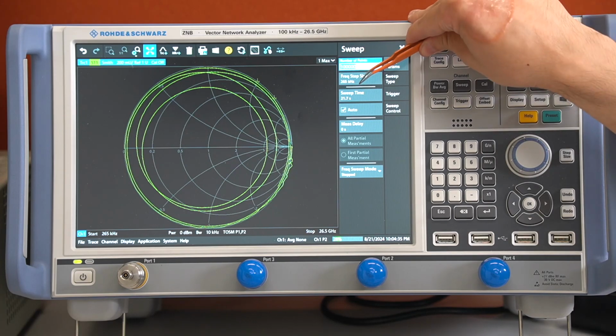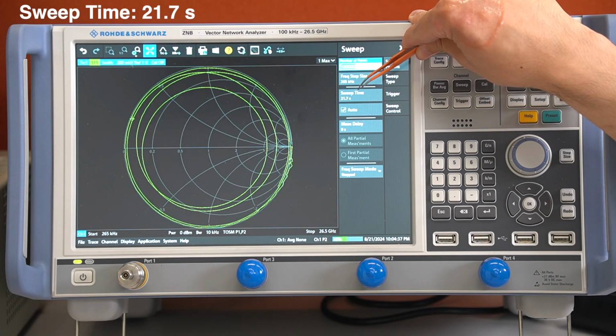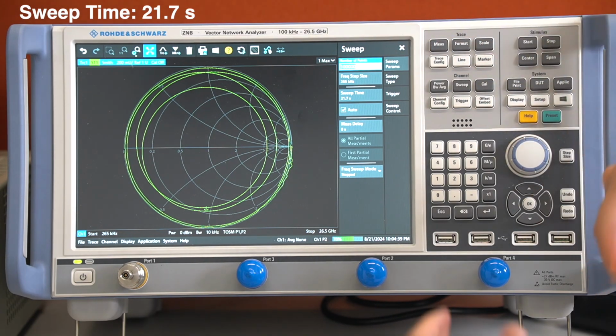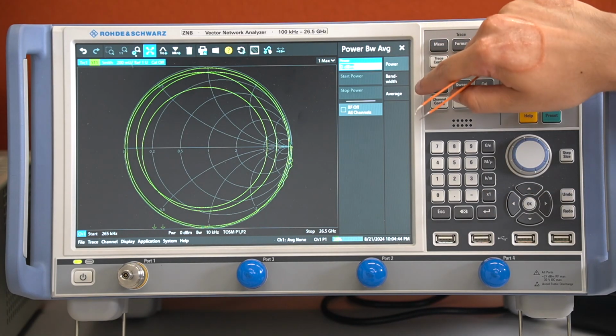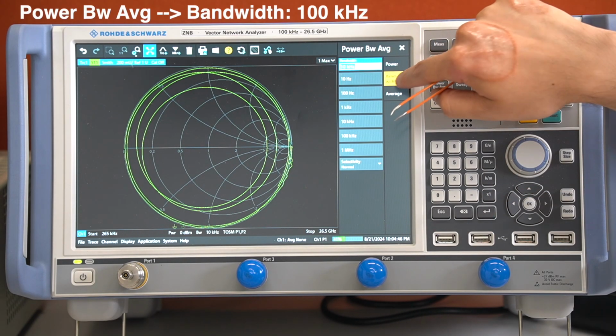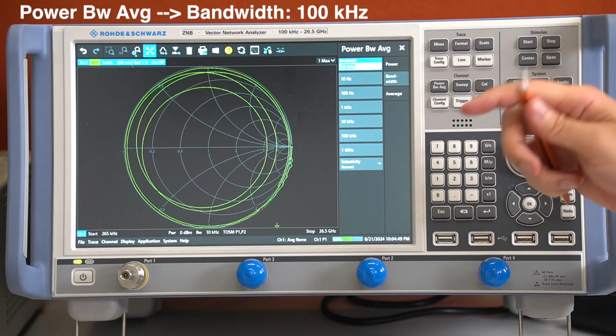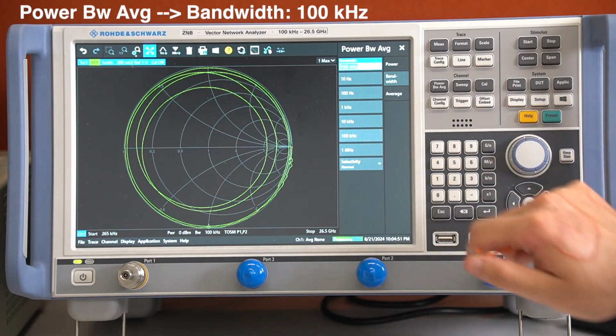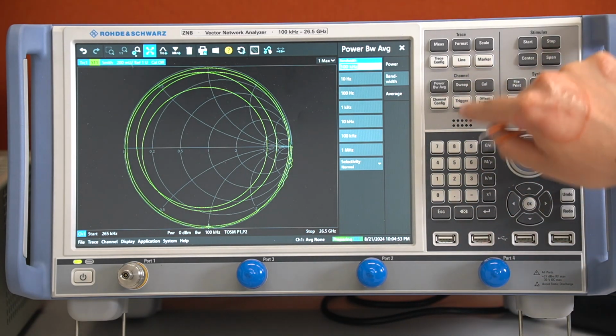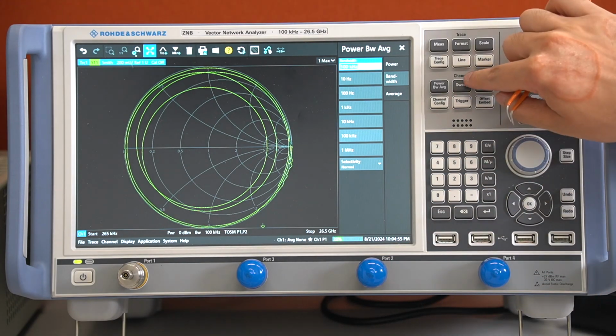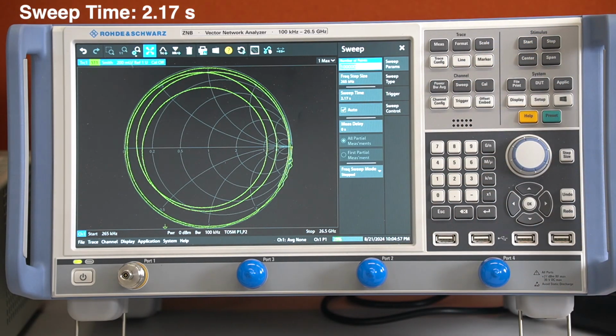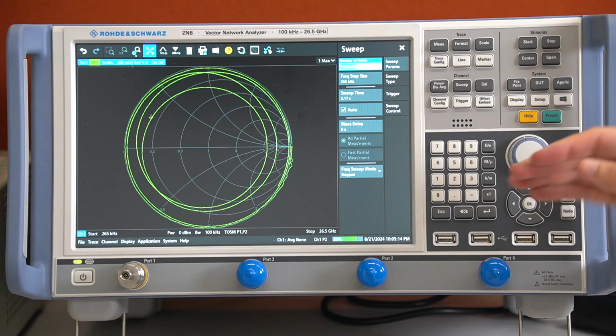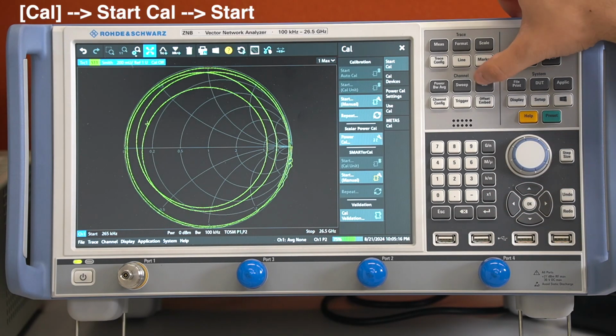But we can see here that our sweep time increased to 21.7 seconds. This is too long. Unfortunately, I have to increase the bandwidth of our intermediate frequency filter to 100 kHz to get the sweep time down to 2.17 seconds. And now let's start again with calibration.